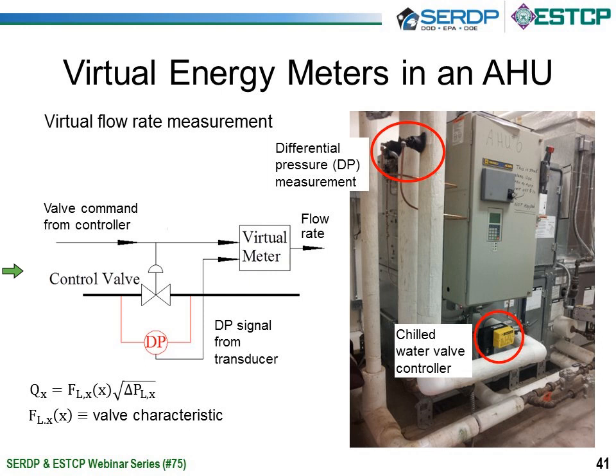If you focus in on the diagram of the system here in the middle of the page, you'll notice at the top we have a valve command from the controller going to the control valve for the chilled water for an air handling unit. That signal also goes to the box at the top right of the diagram that's labeled virtual meter. Virtual meter is nothing more than the algorithms running on some processor. So basically I'm describing the algorithms that are implemented in that box. We also add measurement of the pressure difference across the control valve. This is used then in the virtual meter along with the valve command to determine the flow rate.